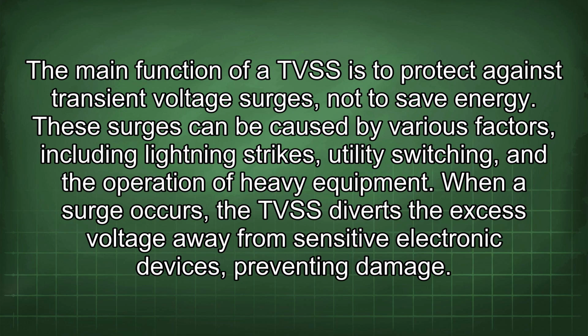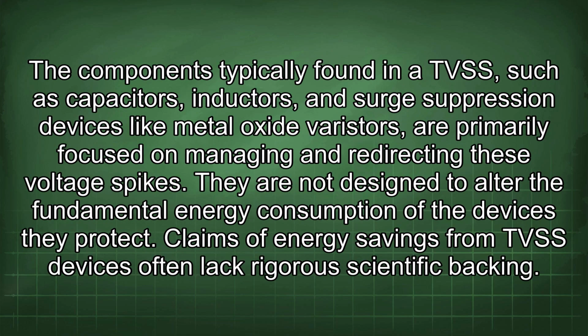These surges can be caused by various factors, including lightning strikes, utility switching, and the operation of heavy equipment. When a surge occurs, the TVSS diverts the excess voltage away from sensitive electronic devices, preventing damage. The components typically found in a TVSS, such as capacitors, inductors, and surge suppression devices like metal oxide varistors, are primarily focused on managing and redirecting these voltage spikes. They are not designed to alter the fundamental energy consumption of the devices they protect.